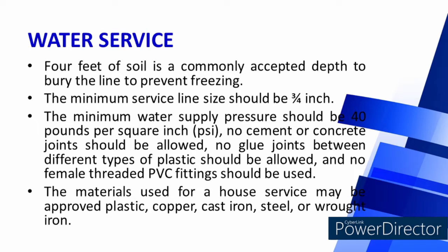Water Service: Four feet of soil is a commonly accepted depth to bury the line to prevent freezing. The minimum service line should be ¾ inch. The minimum water supply pressure should be 40 pounds per square inch. No cement or concrete joints should be allowed. No glue joints between different types of plastic should be allowed. No female-threaded PVC fittings should be allowed. Materials used for a house service may be approved plastic, copper, cast iron, steel, or wrought iron.